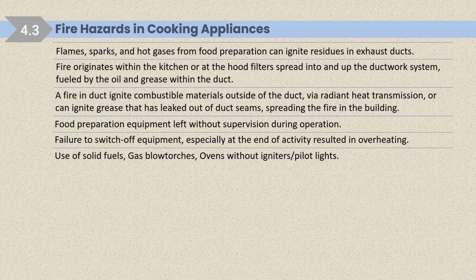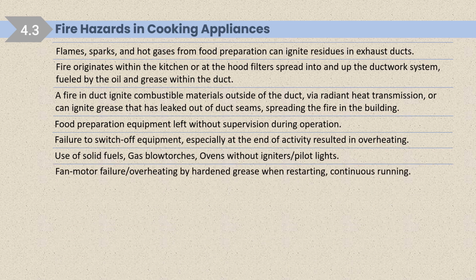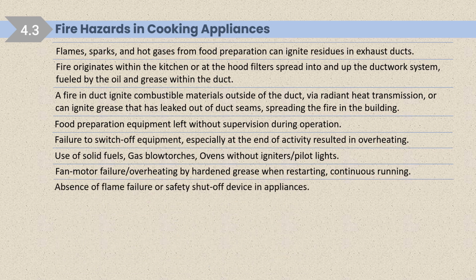Use of solid fuels, gas blow torches, ovens without igniters, pilot lights. Fan motor failures. I've seen one fire incident that was caused by fan motor failure. Overheating by hardened grease when restarting, continuous running of the exhaust system, absence of flame failure or safety shut-off devices in appliances.